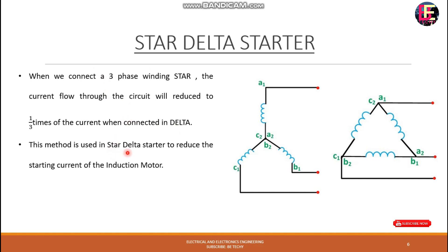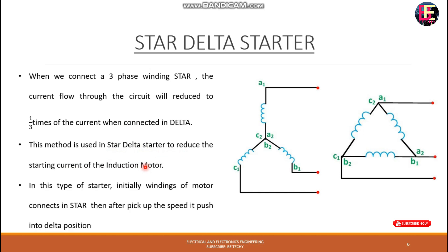This method is used in the Star-Delta starter to reduce the starting current of the induction motor. When the motor picks up speed, the connection is changed to delta. In this type of starter, initially the windings of the motor connect in star, then after picking up speed, switch into the delta position.